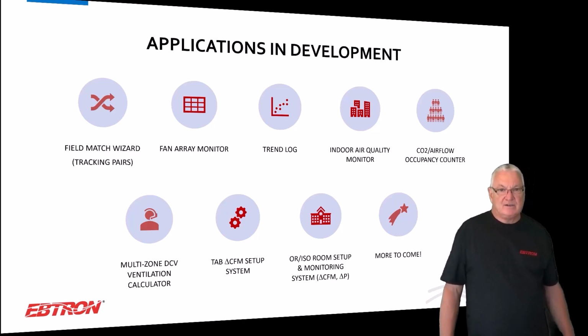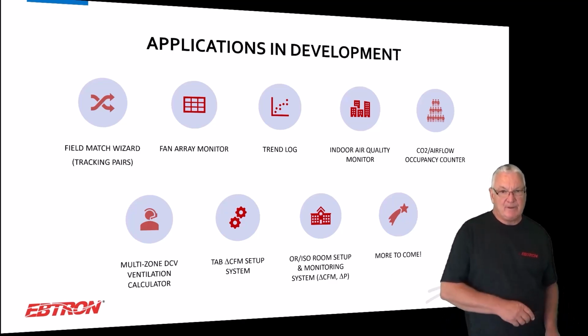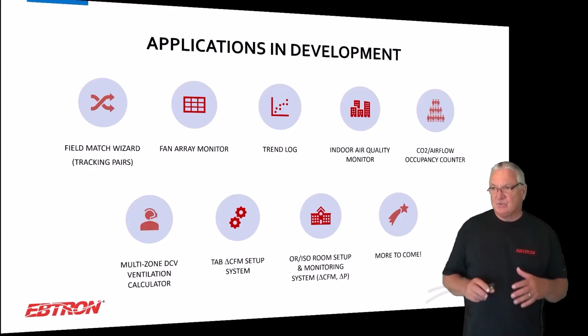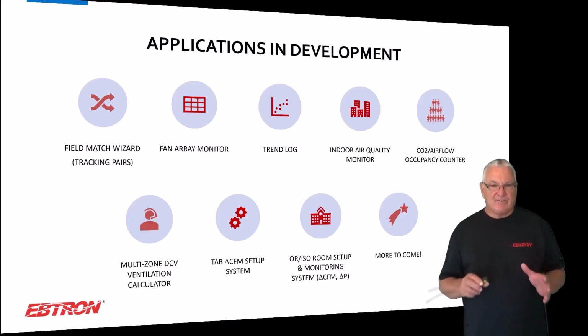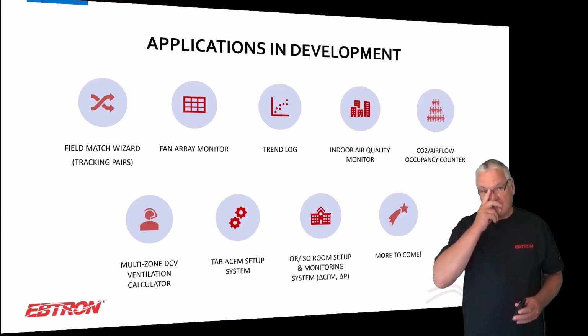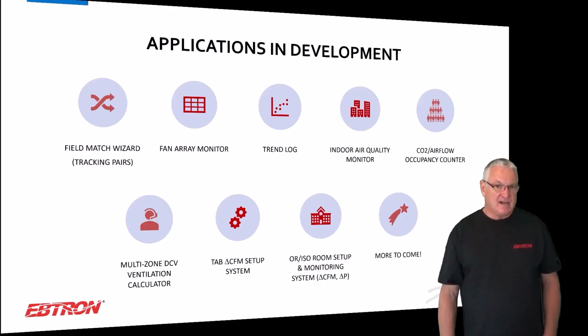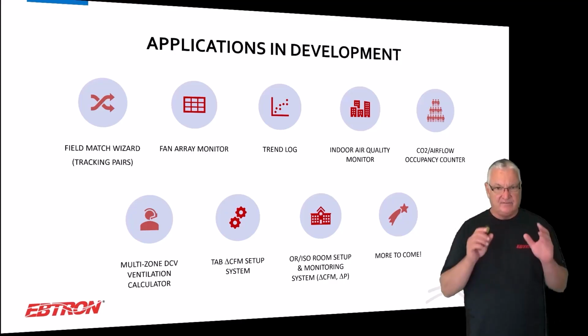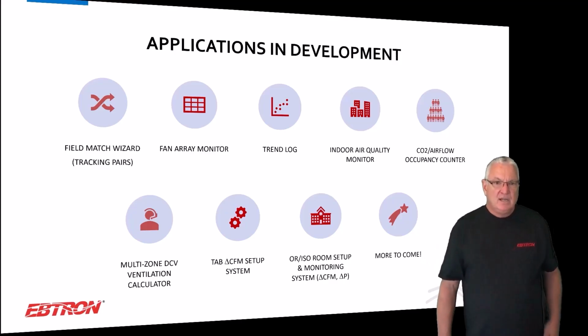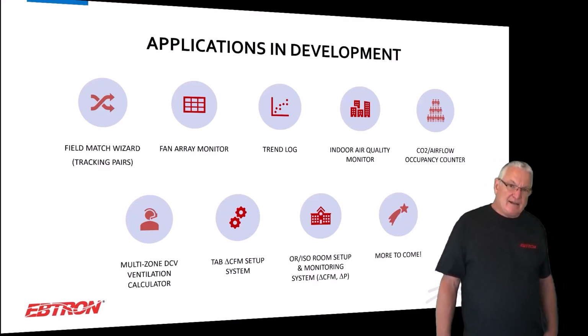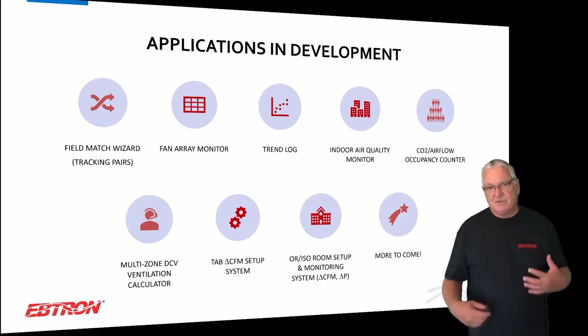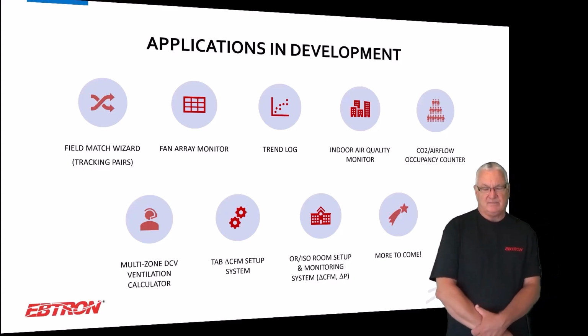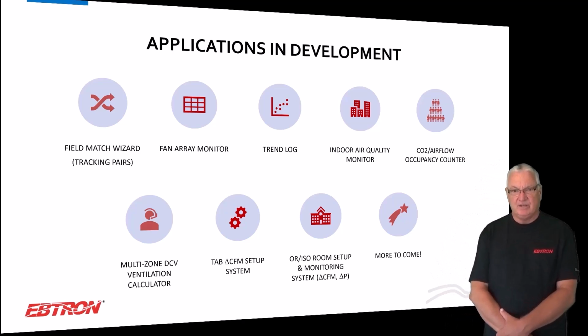Fan array monitor is another one that I want to see happen soon. If you look at our display app, it shows you the actual average CFM output of the devices, but there are people out there that have requested, hey, I want an app that I can click on and look at my fan array and see the flow from each one of my fans. And that's fine. So that's a fan array app. The trend log app may be put on hold because most of the time people using this have a building automation system that can do the trend log, but obviously we can do it.